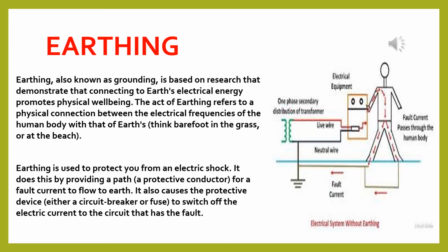In houses, near the kilowatt hour meter, that is a meter used for measuring electrical energy consumed, local earthing is made. For this, a hole 2-3 meters deep is dug in the ground, in which a thick copper wire or rod surrounded with a hollow insulating pipe is put. A thick copper or iron plate of size 50 centimeter square is attached to the end of the wire and is buried in the ground. For good earth connection, the plate is surrounded by a mixture of charcoal and salt. Water is poured from time to time through a pipe to keep the ground damp.